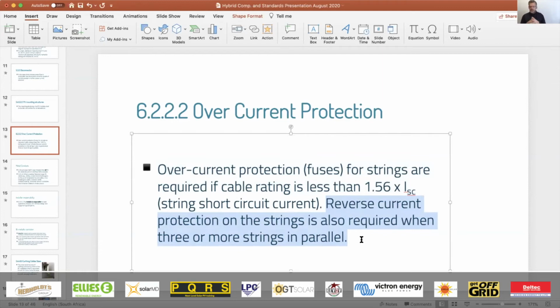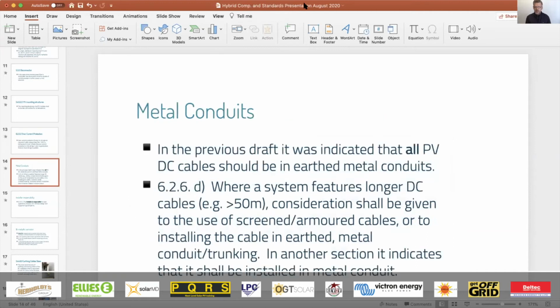So, guys, again, the reverse current coming back into play, and over here it gives you the cable rating, and it says that if your cable rating is less than 1.56 times the short circuit current of the string, then overcurrent protection is required. I hope that makes sense. If it doesn't make sense, I'll answer a couple of questions when I am done with the presentation.